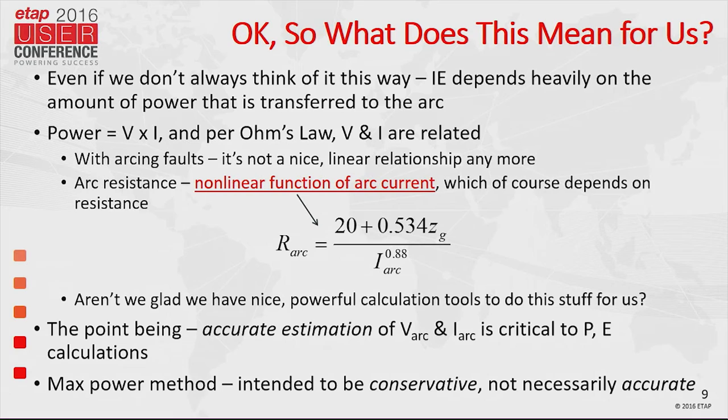Okay, so these guys weren't really specifically testing for arc flash incident energy. Is this really relevant to us? What does it mean for us? Well, think about it this way. Even if we don't always think of it like this, the incident energy depends heavily on the amount of power that's transferred to the arc. Now, that's a step that's kind of buried in our calculation method in IEEE 1584. But if we know the power, we can figure out how much energy. If we know the energy, we can figure out how much of that gets transferred to the worker.